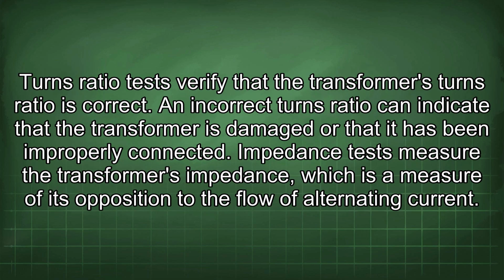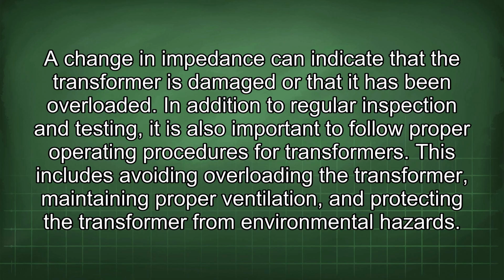Turns ratio tests verify that the transformer's turns ratio is correct. An incorrect turns ratio can indicate that the transformer is damaged or that it has been improperly connected. Impedance tests measure the transformer's impedance, which is a measure of its opposition to the flow of alternating current. A change in impedance can indicate that the transformer is damaged or that it has been overloaded.